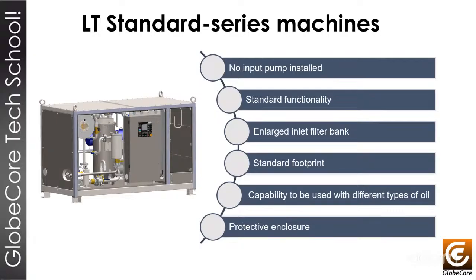As I said before, no input pump is installed in these machines. This series of machines is really the same as the previous CMM and UVM machines, but we have to see different things here. The main difference, as I said, starting with the standard equipment, is that no input pump is installed. The pumping-in function is performed by a vacuum pump, which generates a vacuum in the inlet line, allowing the oil to flow into the machine.